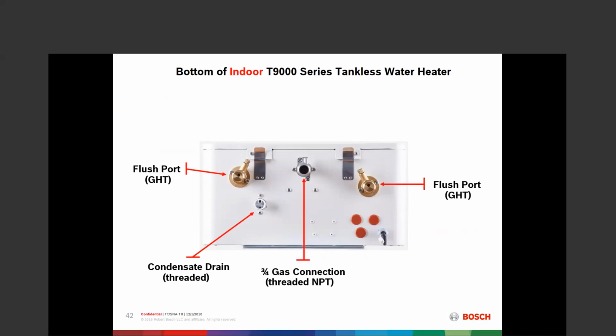Gas connection, it is 3/4 of an inch. Yes, we can connect a 1/2-inch gas line, assuming again the gas pressure is adequate. And then also external of the cabinet, this stub right here is actually the nipple for your manometer for checking gas pressure. That sits right there on that external stub. Cover screws lock the cover in place, and it's held in place functionally with these spring clips. These spring clips are what hold it in place functionally. Knockout plugs, if we're going to connect to an external circulator, connect to an adjacent unit for cascading controls or those kind of things, those plugs are right there inside the cabinet ready to go.